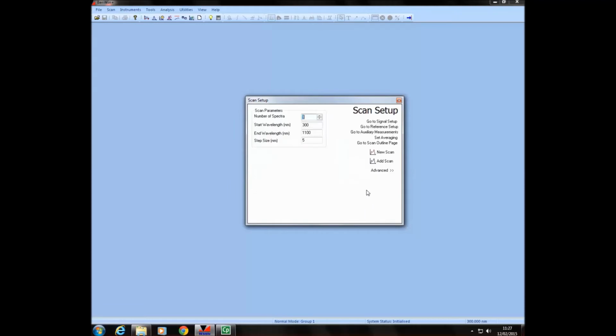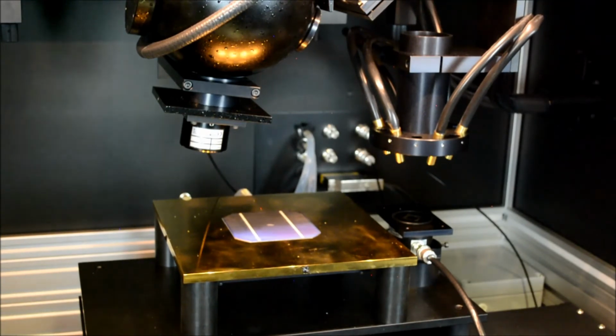Now we can return to scan setup. We will see in advance that data correction is now selected, and we can go ahead and measure the device with calibration in place, so reporting units of spectral responsivity. The silicon reference diode was calibrated 300 to 1100 nanometers, and the germanium reference diode 800 to 1800 nanometers. Wherever one wants to measure a sample over a range that extends beyond the spectral range of one or the other detectors, we have to calibrate with both detectors.